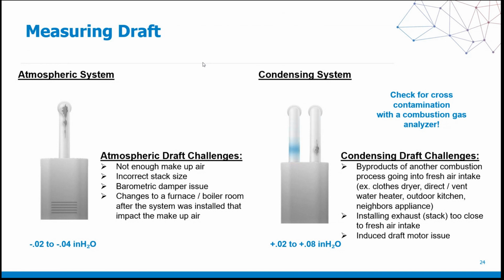Or if a furnace or boiler was sitting in a nice open space and that building owner or homeowner decided to create an enclosed space where they kind of enveloped that boiler or furnace in an actual room and didn't allow it to have enough combustion air, that can create an issue for an atmospheric system.